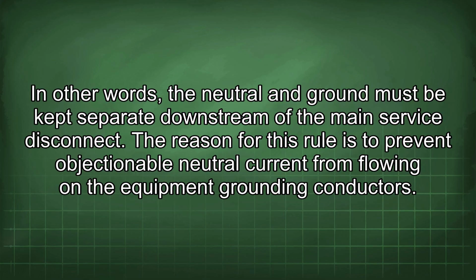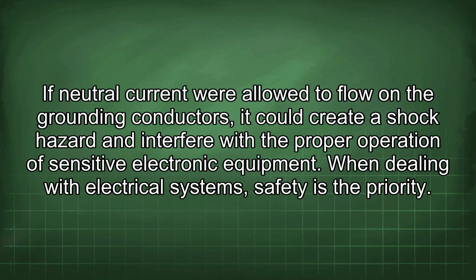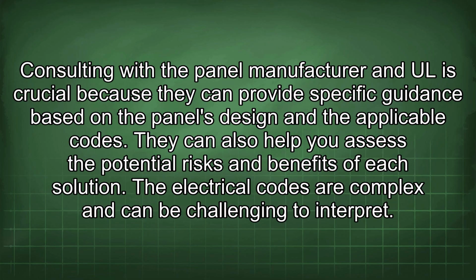The reason for this rule is to prevent objectionable neutral current from flowing on the equipment grounding conductors. If neutral current were allowed to flow on the grounding conductors, it could create a shock hazard and interfere with the proper operation of sensitive electronic equipment. When dealing with electrical systems, safety is the priority. Consulting with the panel manufacturer and UL is crucial because they can provide specific guidance based on the panel's design and the applicable codes. They can also help you assess the potential risks and benefits of each solution.